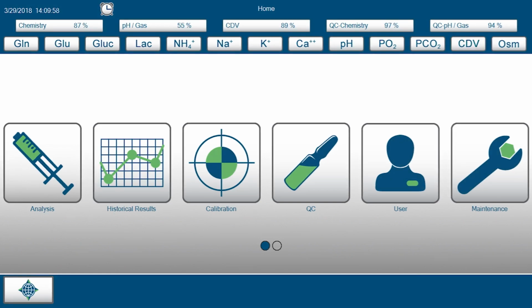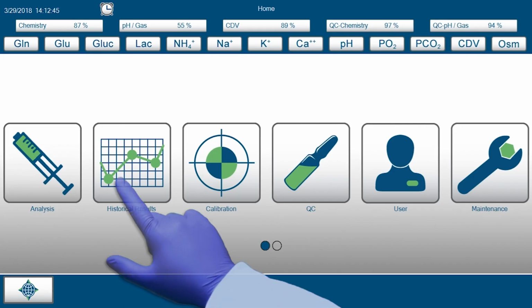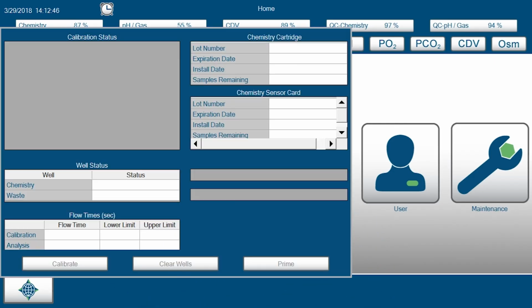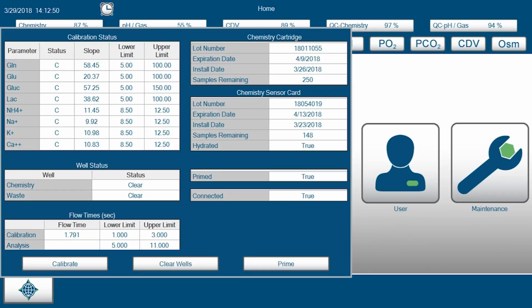You can open up the module status overlay by tapping on each module or any parameter in the module. The module overlay provides more information about the module, including the calibration status, reagent status, well status, flow times, and primed and connected status. You can also initiate some sequences from the bottom of the overlay. The primed and connected status must be true for the module to be available for sampling. If primed displays false, you can start a prime by selecting the Prime button.